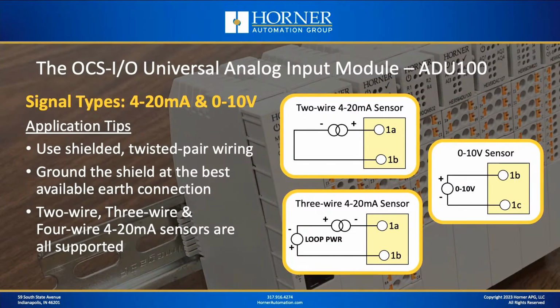Now, why is there more than one 4 to 20 milliamp diagram there? Well, that's because there are multiple different types of 4 to 20 milliamp sensors. You have a 2-wire sensor, a 3-wire sensor, and a 4-wire sensor that are available, and they're all supported. One thing I will mention is this. These are relatively low-level signals, and you should use shielded twisted pair wiring between the sensors and the ADU100. That way, you can properly shunt any EMI or RFI to earth ground if you properly drain the shield for the cable. Okay, so don't cheap out. Use shielded twisted pair wiring. It's not that expensive, and it's the right way to do the application.